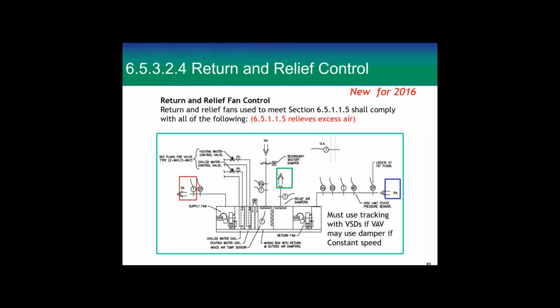Return and relief fan control. So this is for 2016, and we had what we believe to be a problem in building pressurization, in that designers were using all kinds of methods to pressurize a building, and some of them were quite energy inefficient. You know, where they put the sensors, what they were up to. And what happens on building pressurization is you're bringing in more outside air, and when you bring in more outside air, it draws our attention because that outside air needs to be cooled or dehumidified, and it costs energy. So we're trying to minimize the amount of outside air you have to bring in for pressurization, and so we require that you use fan tracking.